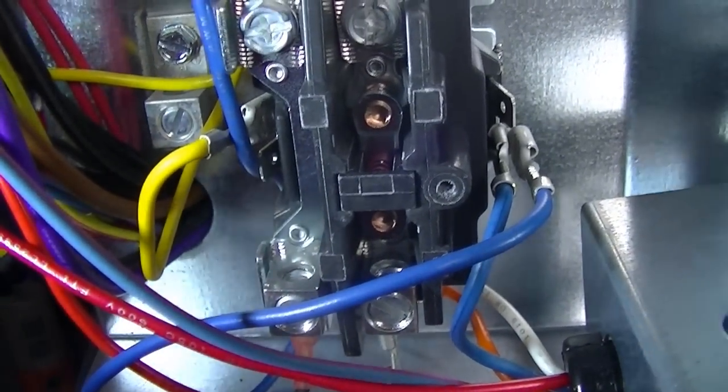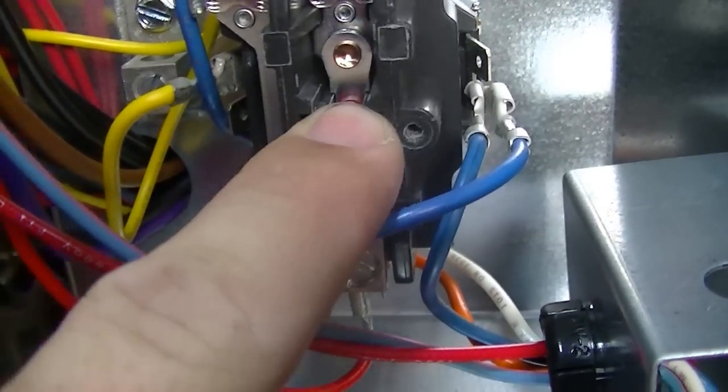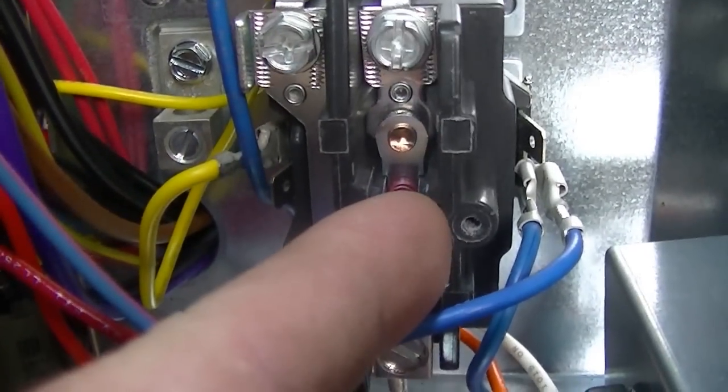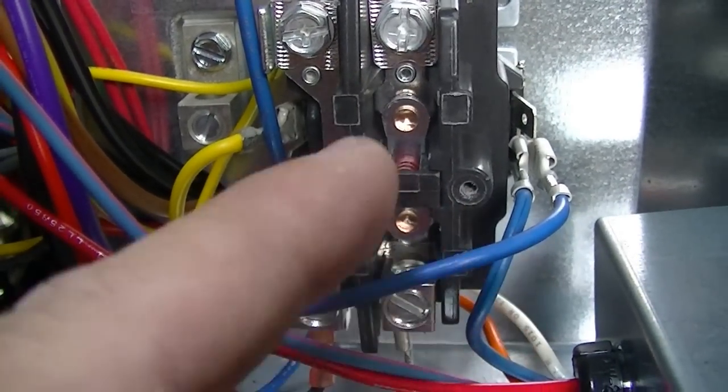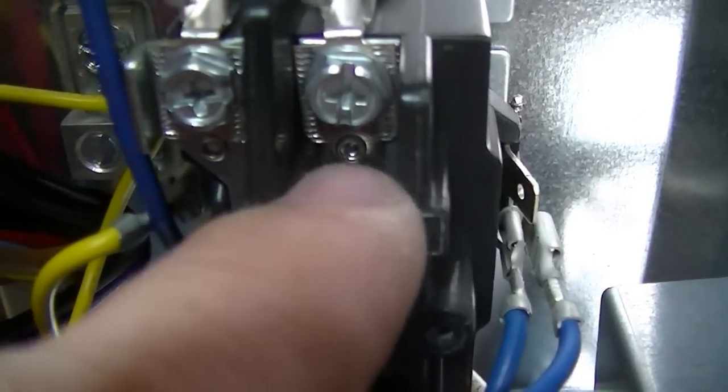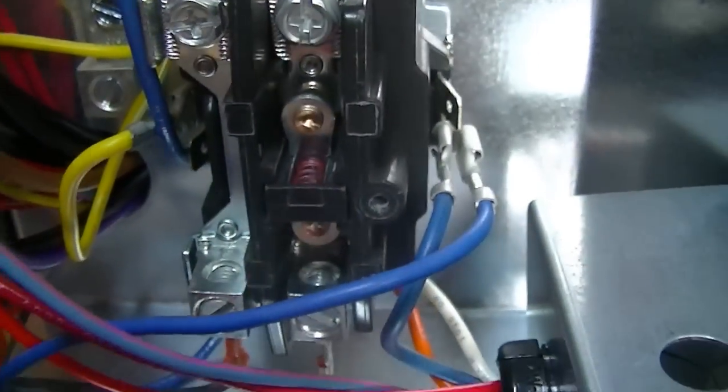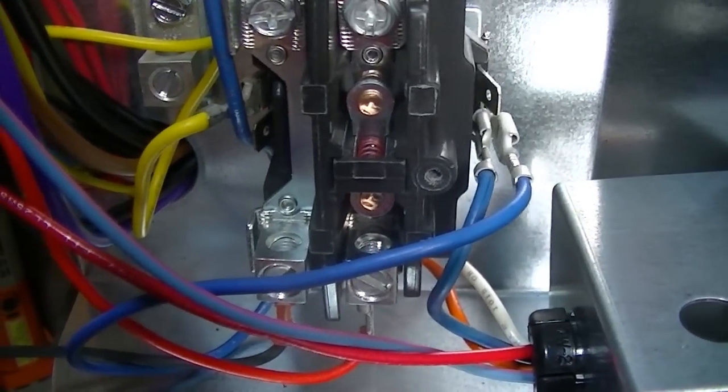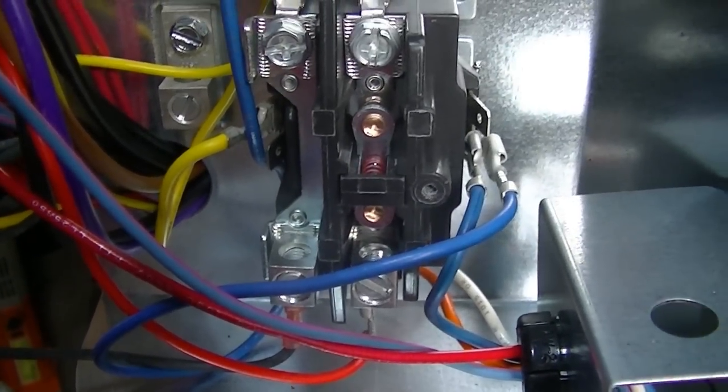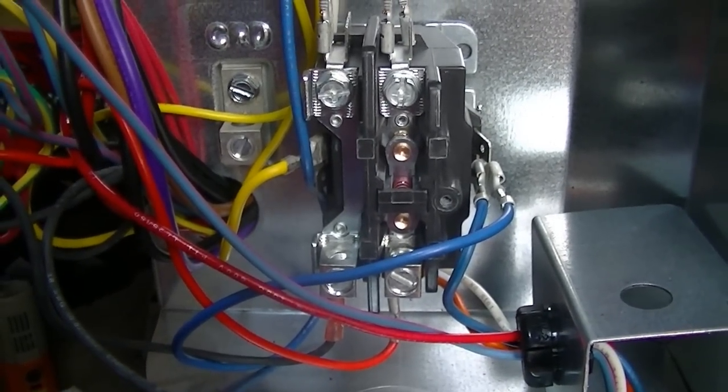Here's a look on the inside of the switch. It's pretty common. Whenever it energizes through the low voltage coil, it draws it in. The voltage passes through. The reason why you have the carbon built up and all the arcing is because sometimes it arcs between these two terminals when it starts to draw in. That's why when you get a real burned up looking contactor, that'll be the reason behind that. Go ahead and change that bad boy out, depending on how rough it looks. It's your judgment. But that's it. That's our contactors for residential HVAC.